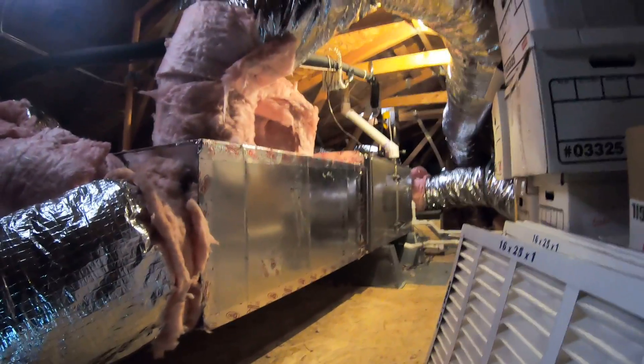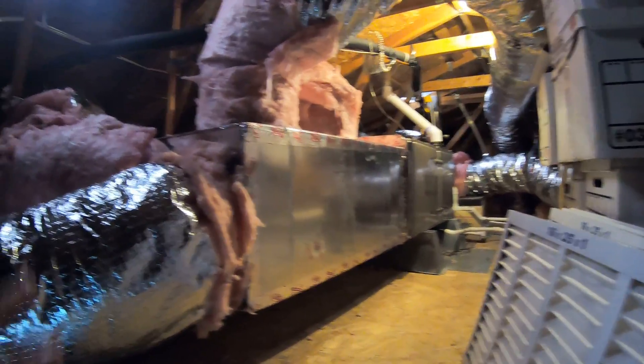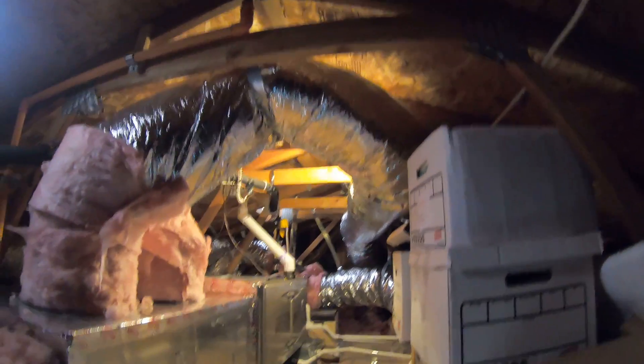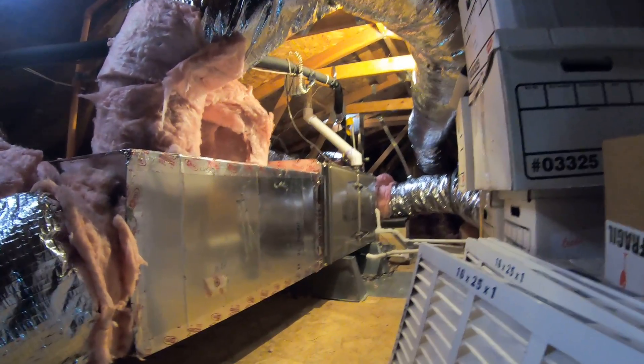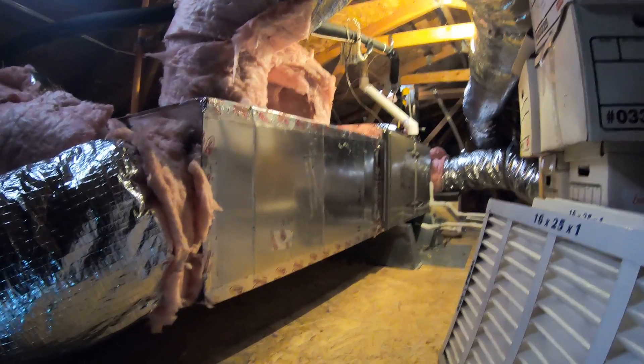This really pulls the heat out of the house a lot faster and gives it very good overall comfort and even comfort. The furnace is located in the attic, so that's how we were able to do this. Before, it just had one duct going down the stairs. We were able to add four 10-inch ducts going to those returns in the ceiling — we ran those all over the attic and as you can see it turned out beautiful.